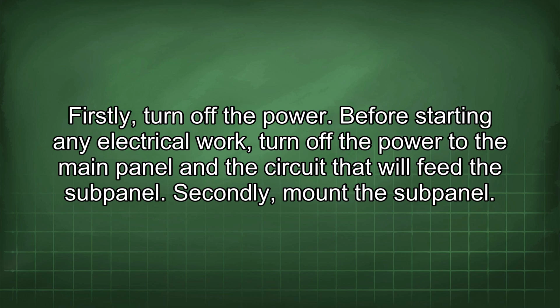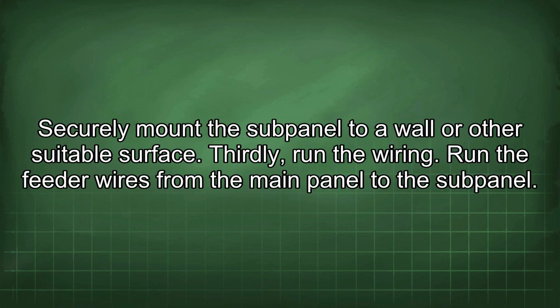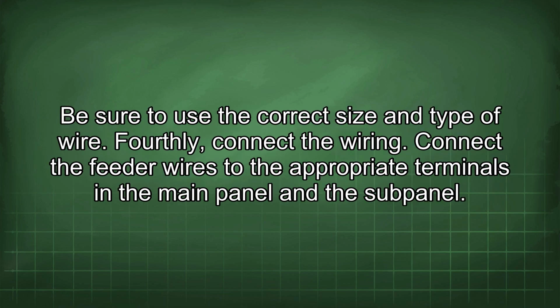Firstly, turn off the power. Before starting any electrical work, turn off the power to the main panel and the circuit that will feed the subpanel. Secondly, mount the subpanel. Securely mount the subpanel to a wall or other suitable surface. Thirdly, run the wiring. Run the feeder wires from the main panel to the subpanel. Be sure to use the correct size and type of wire.